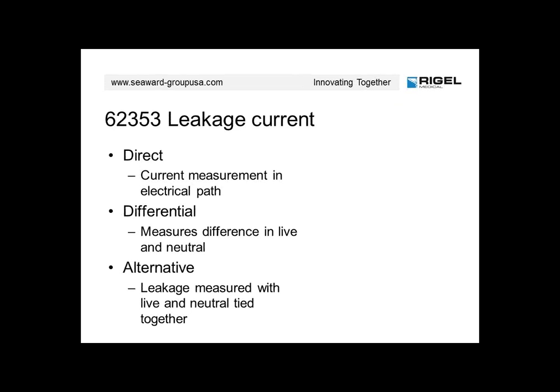So leakage current, a couple of options here now. Direct is what was done with 60601. Two indirect methods have been added to this standard: the differential method and the alternative method. Differential will have the hot wire and the neutral wire go through a small current transformer, and in the differential mode, as you may have guessed at this point, it will look at the difference in the current of the hot wire versus the neutral wire. And then the difference would be defined as leakage current.